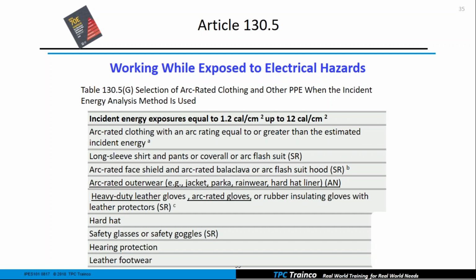So what I like about this, and I became aware that many people in my classes that I teach didn't even know this existed in the back of the document, is that they wanted to mix the two methods together when they chose their PPE, which we never could do. This really spells it out for us. From 1.2 calories all the way up to 12, we have to have an arc-rated clothing system that's equal to or greater than the estimated incident energy. So I look at my label, and I see that I've got 10 calories per centimeter squared of incident energy. I can put a 12 cal shirt on. That's no problem. I do not have to put a flash suit on because it says long sleeve shirt and pants or coverall or arc flash suit.